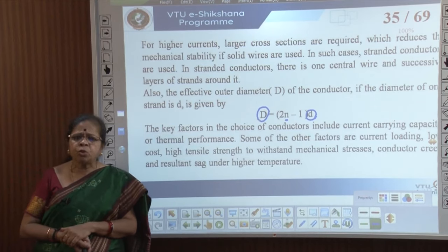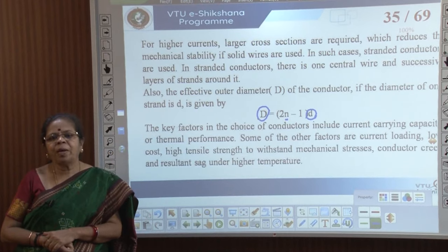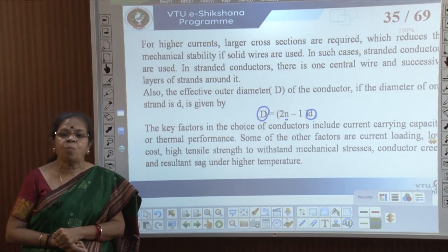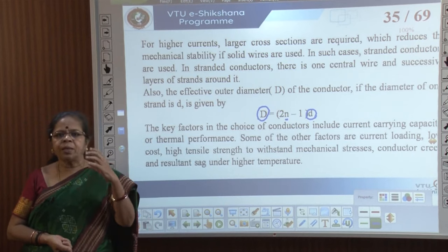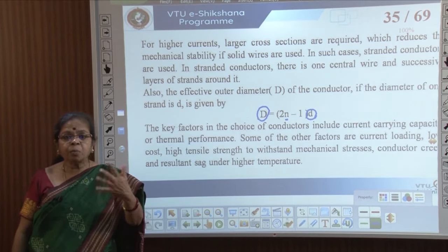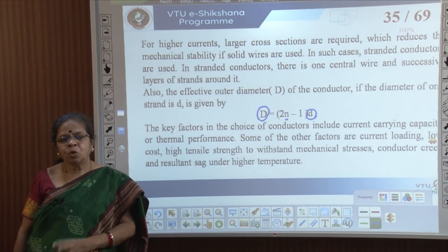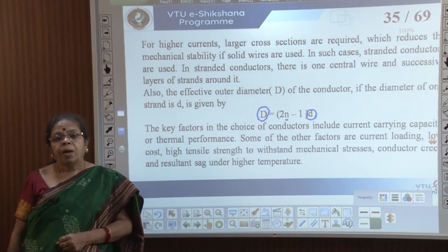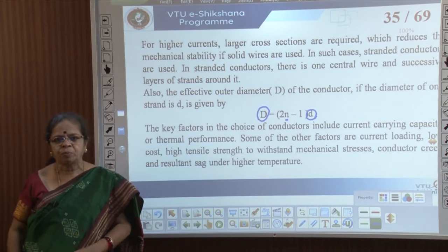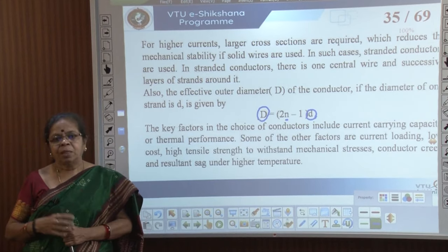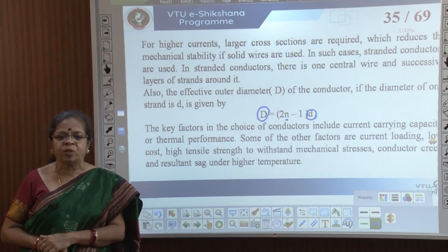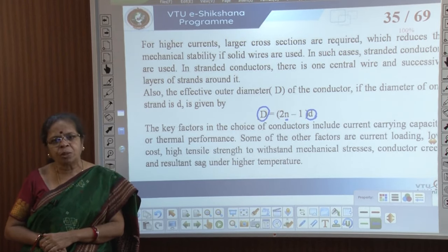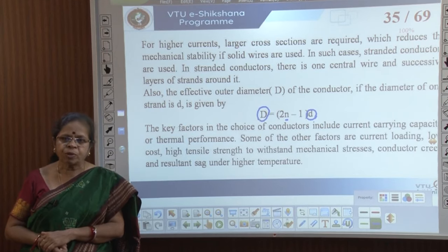When choosing a conductor, the main factors are: current carrying capacity, also called thermal performance — as current flows, the conductor heats up, and it must not heat so much that it melts. Other factors include cost, tensile strength — whether the conductor is strong enough to withstand mechanical stresses from wind — and sag. These factors determine the choice of material used for the conductor.